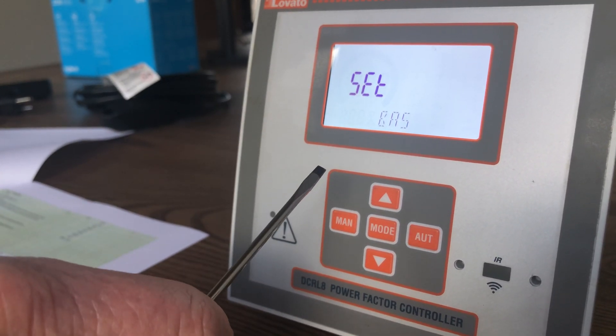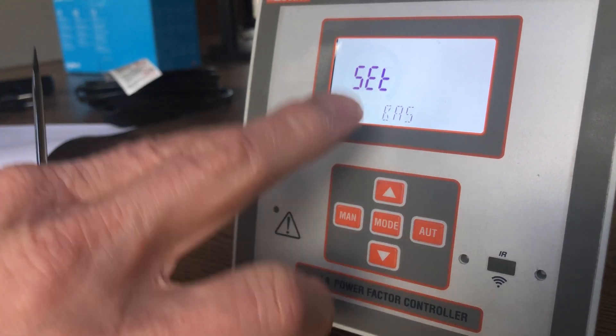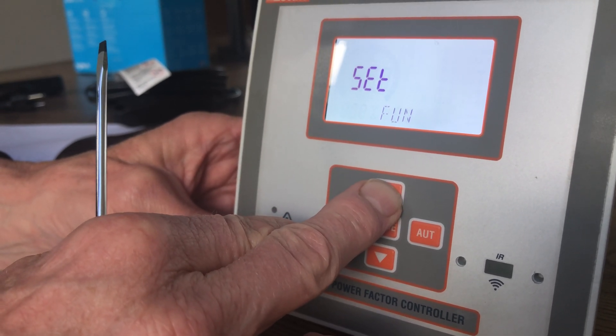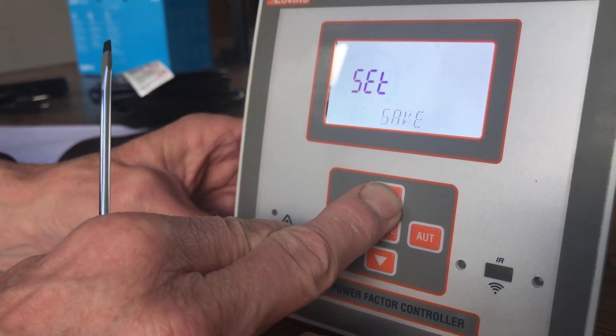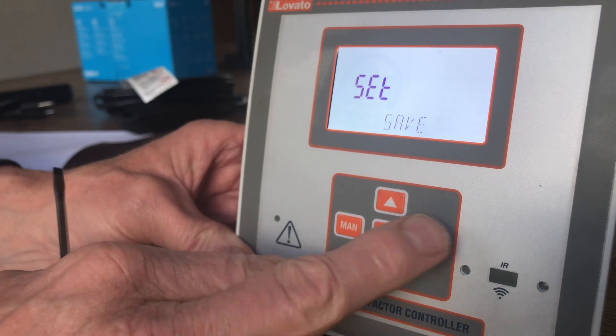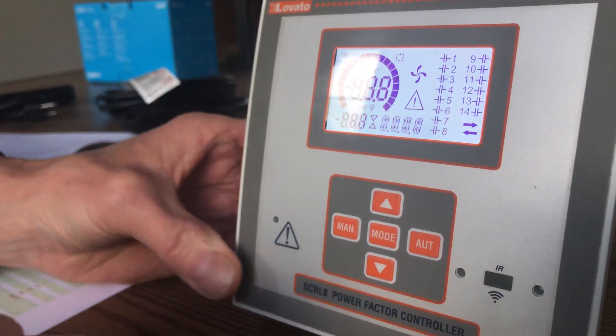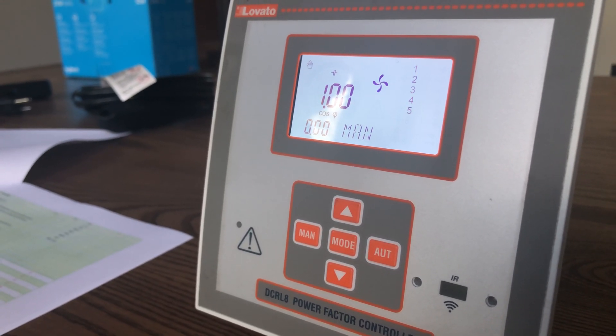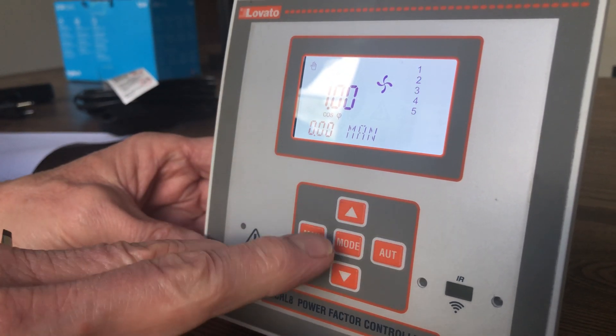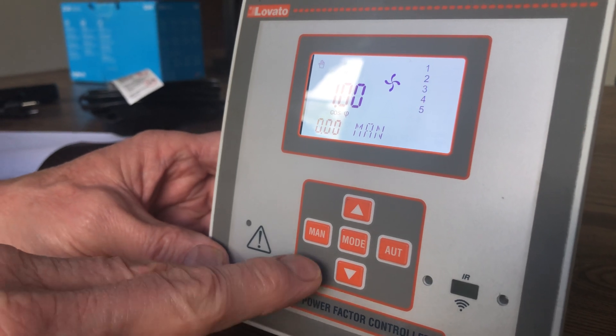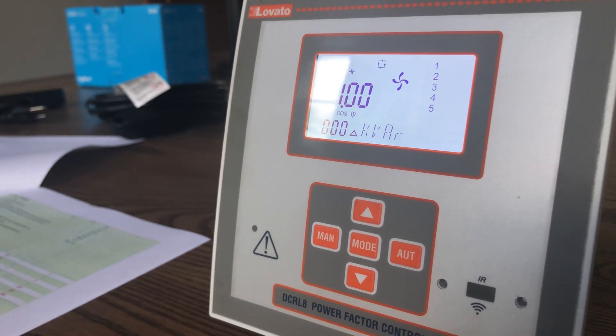Now we've made changes in here but we haven't saved them, so this is really important. Once you get all the way back to BAS — basic — you have to use the up arrow key and advance until you get to SAVE. Once you hit SAVE, you hit AUTO, and it's going to reboot the controller and save those settings for you. Then back to manual — if you want to put the meter back in auto mode, you simply hit AUTO at this point and you're back to auto mode. And that's it for the basic settings.